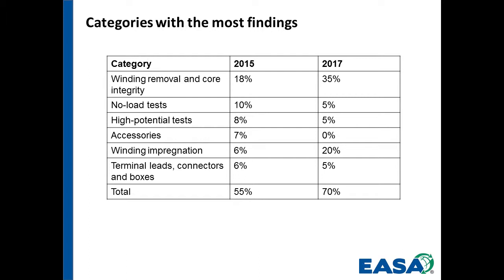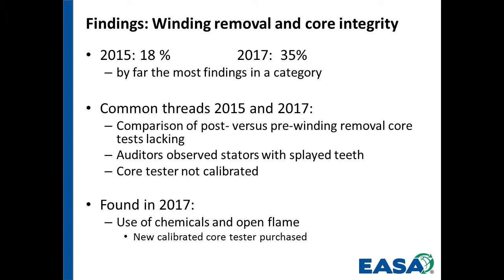If you scan down a little to winding impregnation, it went from 6% to 20%. So things to do with winding are pretty big on the list as far as potential for nonconformance. Other things: no load tests and so on. We'll look at some of these items in more detail. The winding removal, core integrity, 2015 to 2017. Most findings, common thread in 2015 and 2017.